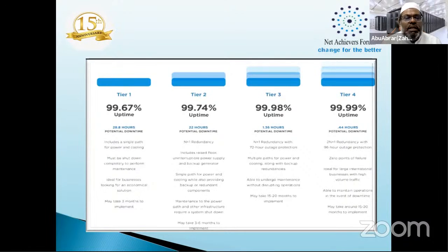Then tier 2, N+1. It means I have one UPS, and I have another one. Maybe the source will be only one, but it can be separated between the UPS. So this type has a bit more advantage over tier 1: N+1 redundancy, and it includes a raised floor, uninterrupted power supply, and backup generator. It has a generator, by the way. You will not have the generator in tier 1.